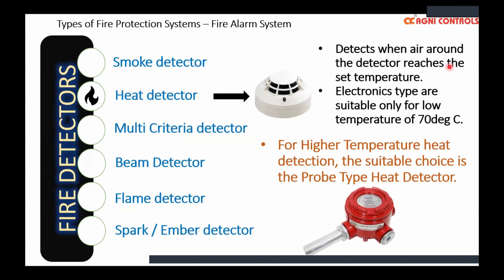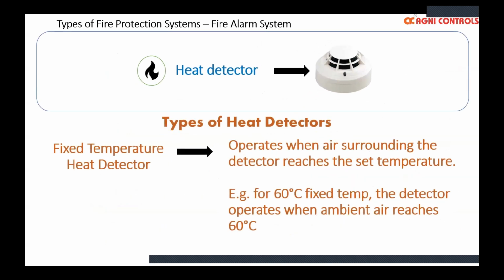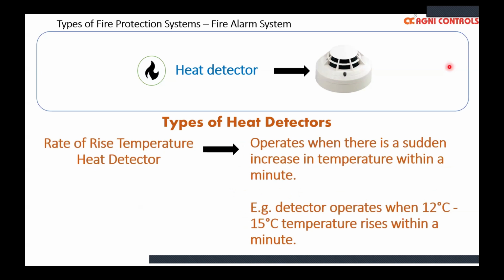Going on to heat detectors, they are available based on different technologies. Fixed temperature heat detectors respond when the ambient air temperature reaches the set temperature of the detector. For example, if you have a 60-degree heat detector and the ambient air reaches or crosses 60 degrees, the detector will operate and give you an alarm. A rate of rise detector operates when there's a sudden increase in temperature within a specific time period, and it gives a heat detector alarm.